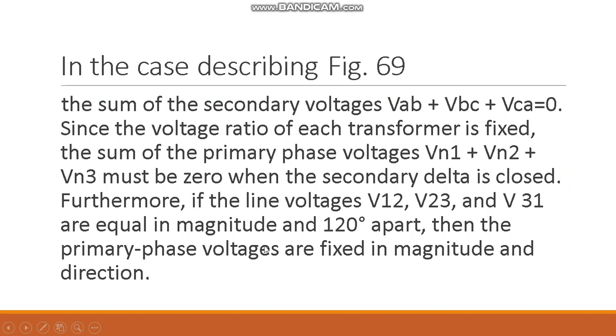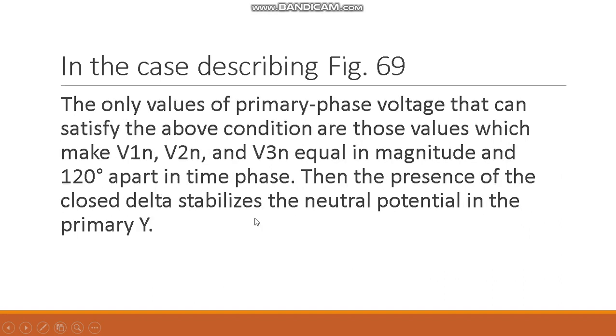If the line voltages V12, V23, and V31 are equal in magnitude and 120 degrees apart, then the primary voltages are fixed in magnitude and direction. The values of primary phase voltage that can satisfy the above condition are those which make V1N, V2N, and V3N equal in magnitude and 120 degrees apart in time phase. Then the presence of the closed delta stabilizes the neutral potential in the primary Y.